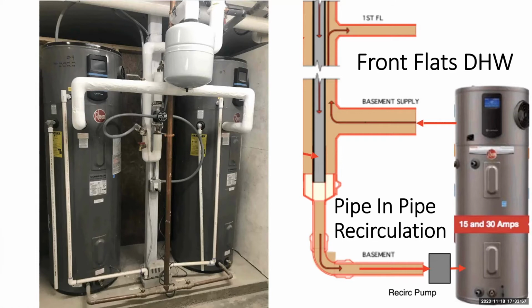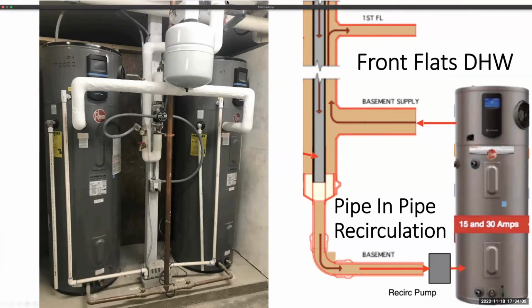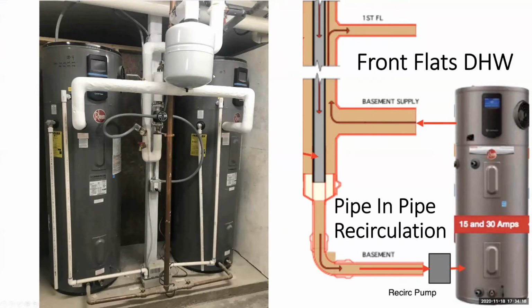That's very energy efficient. You use about a third less energy if you just turn off that electric resistance 'backup,' which is extremely rarely needed. It has a hair trigger about turning on electric resistance, based on monitoring almost 500 of these tanks over the last 6 years across various brands. You don't need the electric resistance—store it at 140 Fahrenheit, run heat pump only mode, and everything's awesome.